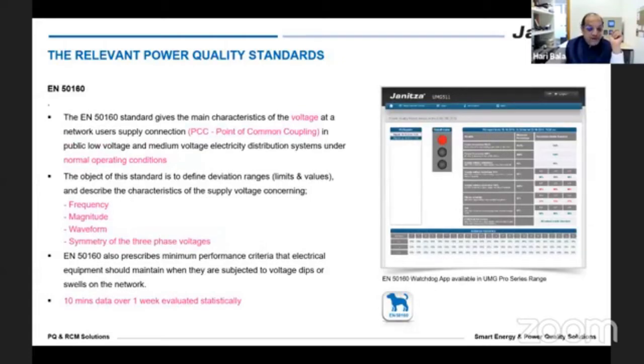Then EN 50160. If you look at the reasons given by MERC about the voltage levels to be maintained, including sag and swell, it all complies with EN 50160. So they talk about frequency, voltage magnitude, waveform, how it has to be, and unbalance in voltage and all those things. Generally, these standards do a statistical evaluation. That's what is very important. They do a statistical evaluation and then present you with EN 50160.